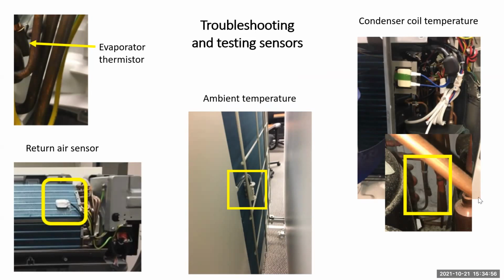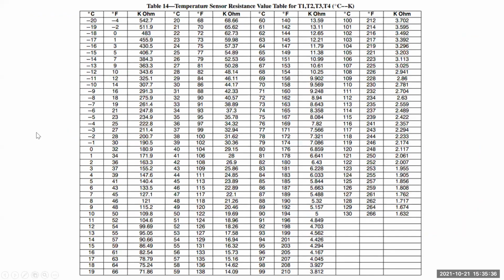So here we're going to go over the sensors. If you have a faulty sensor, 9 times out of 10, you're going to get a fault code. So T1 sensor, where's that at? T1 sensor's room temperature sensor. T4 is your ambient sensor. T3 is your condenser coil, which is usually pretty hard to see. T5 is a compressor discharge sensor. And over here we have your evaporator sensor, which is the T2 sensor. And we can check this against the chart, and all these charts are in the service manuals.